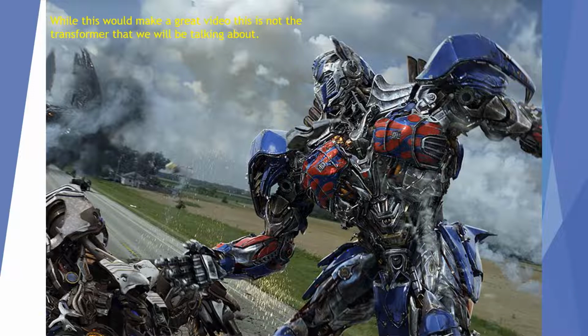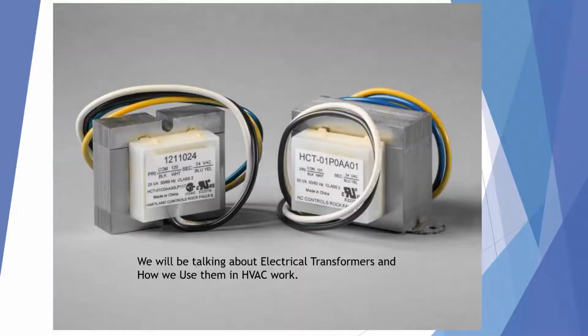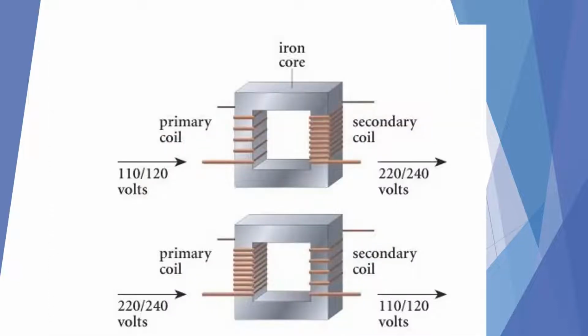While this would make a great video, this is not the transformer that we will be talking about today. We're going to talk about electrical transformers and how we use them at HVAC work. There's basically two different transformers that we use in HVAC. The first one is a step-up transformer, which steps voltage from a lower voltage to a higher voltage. In this example, we have 110, 120 volts on our primary side, and we're stepping it up to 220, 240 volts on the secondary side.